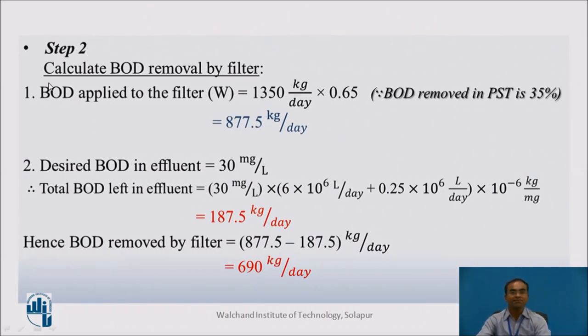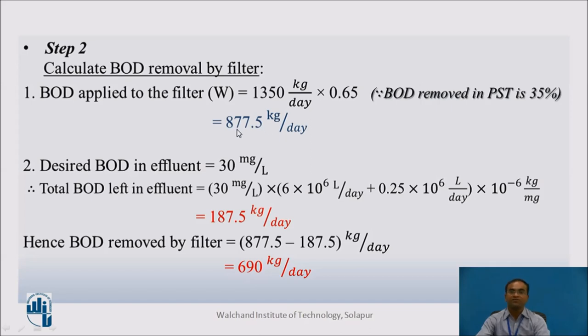Step 2: Calculate the BOD removal by the filter. First, calculate the BOD applied to the filter. Since 35% of BOD is removed by the primary clarifier, the remaining 65% enters the trickling filter. BOD applied to filter = 1,350 kg/day × 0.65 = 877.5 kg per day.